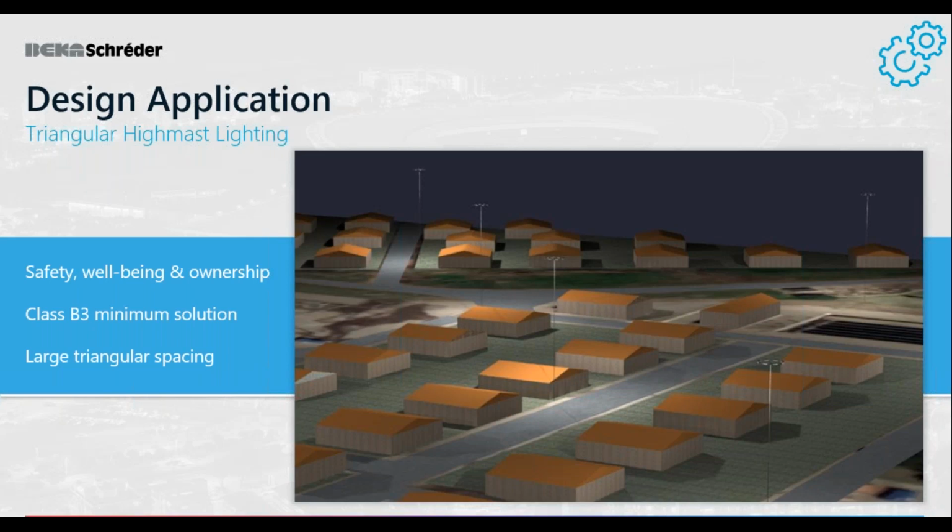What's also very important with LED technology, and the OMNIBLAST-E range really lends itself to this, is that we can apply programmable dimmable drivers into the luminaire, which further reduces the cost of electricity over time. If you can imagine, depending on the time of the year, when it gets dark, we'll use 1600 or 1800 as one of the timings. These luminaires switch on at 100% until about 10 o'clock at night or 2200. They stay at 100%.